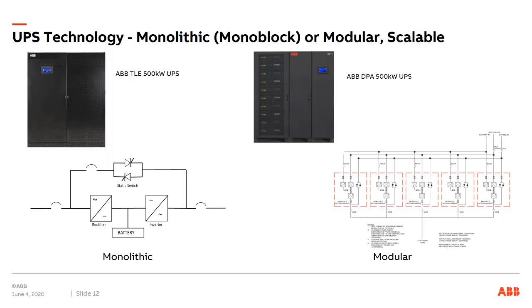The benefit with this is that there's much greater scalability compared to a monolithic UPS. The customer can buy the 500 kW frame, and then, depending on what they need today, put 1 or 2 or 3 power modules in there and add more as they need them, postponing the capital expenses. But both the monolithic and the modular can be paralleled to get to bigger power than 500 kW. And these are just examples.